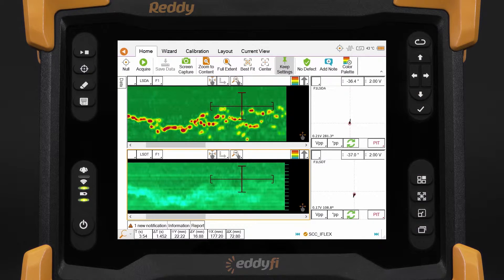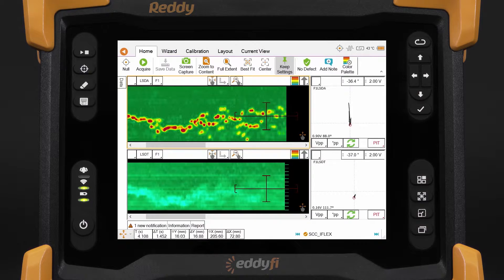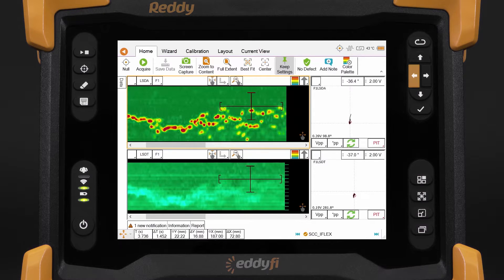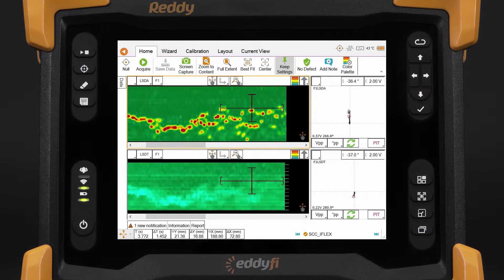Let's say you want to set your cursor to precisely measure one individual defect in the scan. Select the C-scan where you want to set your cursor and move it on top of the defect you want to measure. The arrow allows much more precise movement than the touch screen.